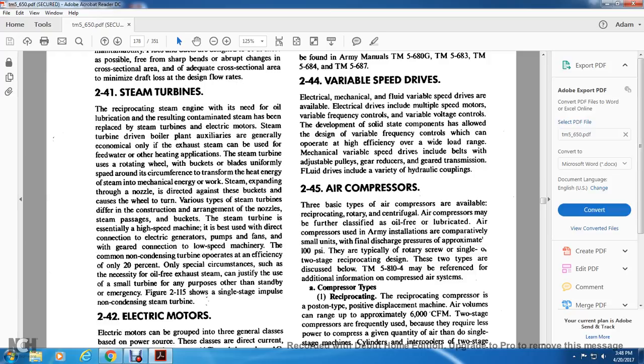2-41. Steam turbine. The reciprocating steam engine, with its need for oil lubrication resulting in contaminated steam, has been replaced by steam turbines and electric motors. Steam turbines driven boiler plant auxiliaries are generally economical only where the exhaust steam can be used for feed water heating. The steam turbine uses a rotating wheel with buckets and blades uniformly spaced around the circumference to transform the heat energy of steam into mechanical energy. The engine works with steam expanding through a nozzle directed against the buckets, causing the wheel to turn. There are various types of steam turbines, with different construction arrangements of the nozzle, steam passage, and bucket.